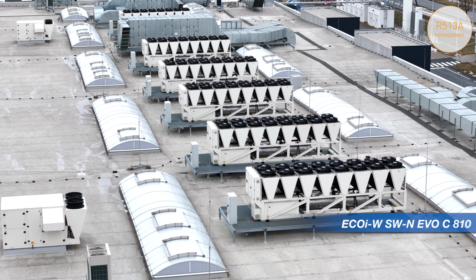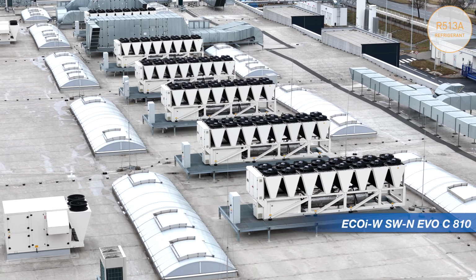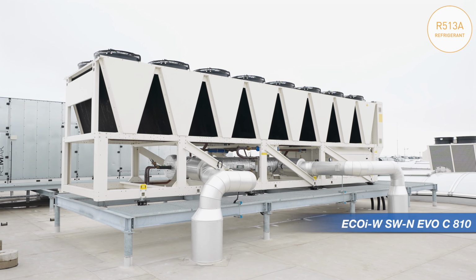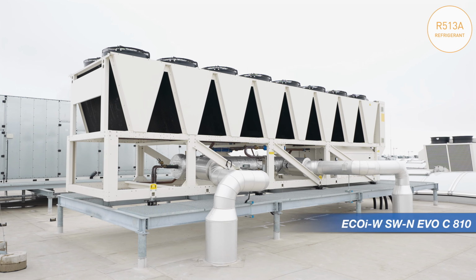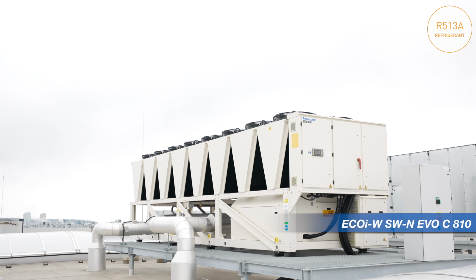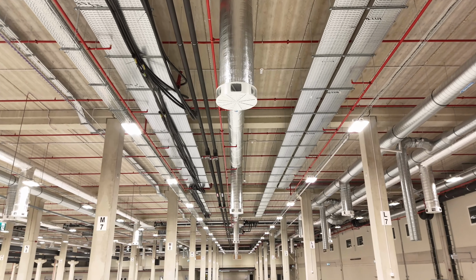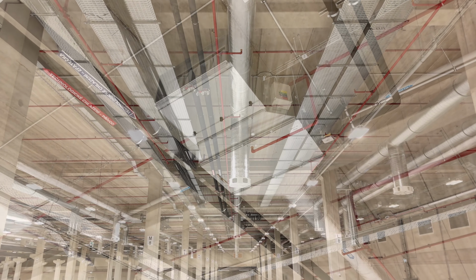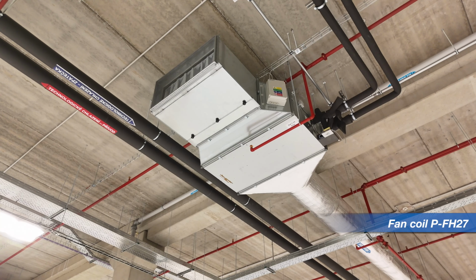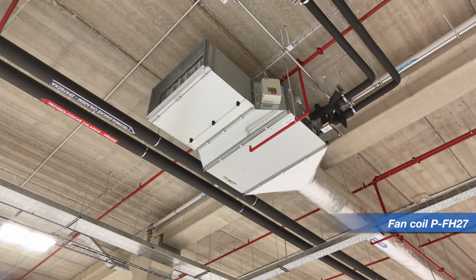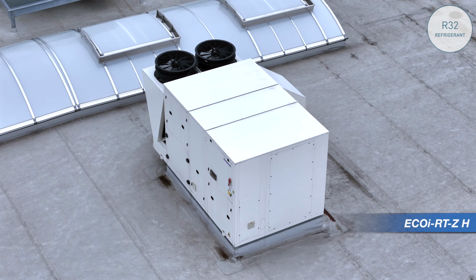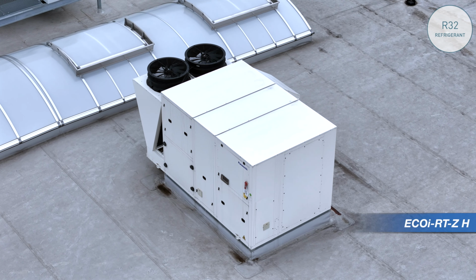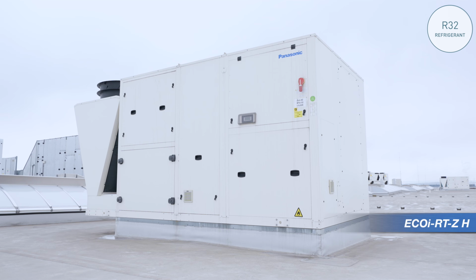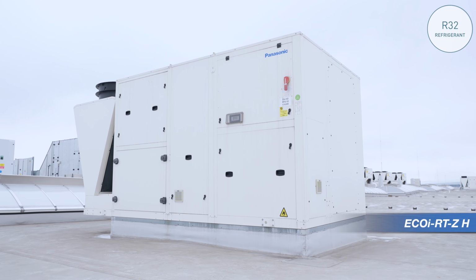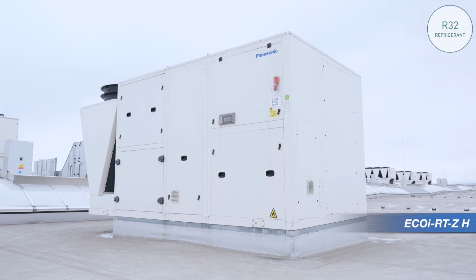The source of chilled water for these air handling units is 6 Panasonic chillers with the environmentally friendly refrigerant R513A, each with a capacity of 800 kilowatts. For cooling in the production halls, an additional 57 fan coil units were used, with a total cooling capacity of 1,500 kilowatts. In the section of the production area where the use of air handling units was not optimal, 3 rooftop units with refrigerant R32 were installed, with a total capacity of 350 kilowatts.